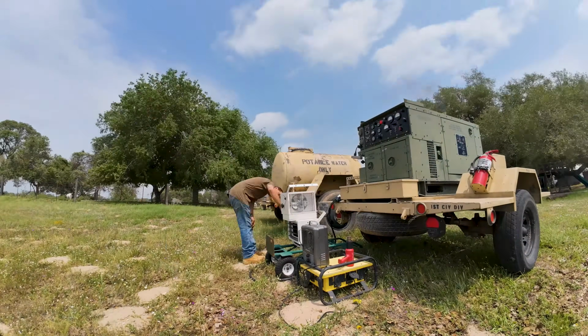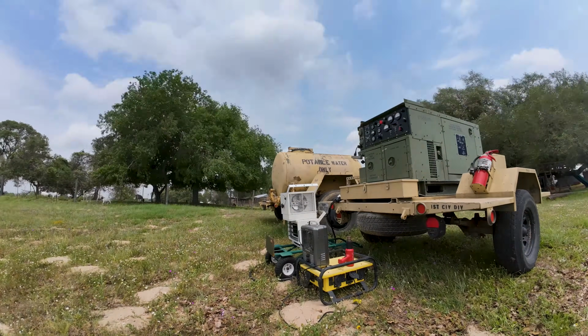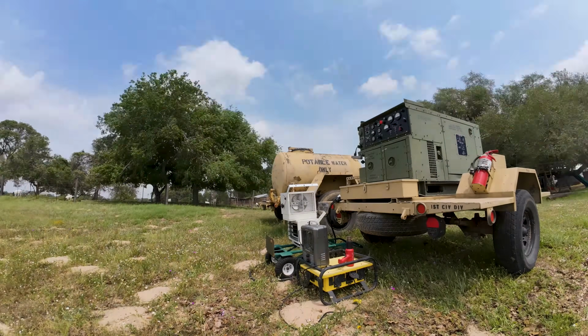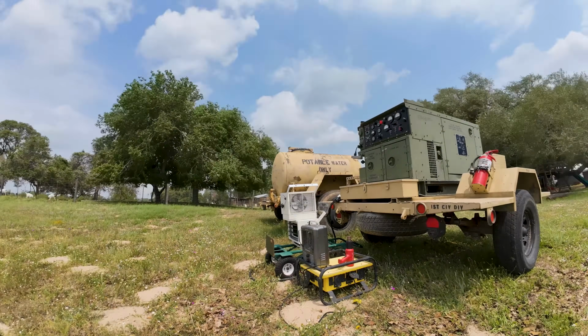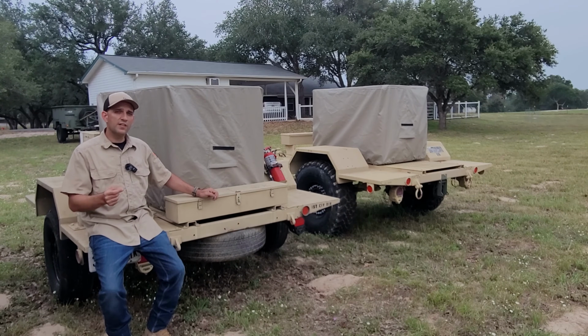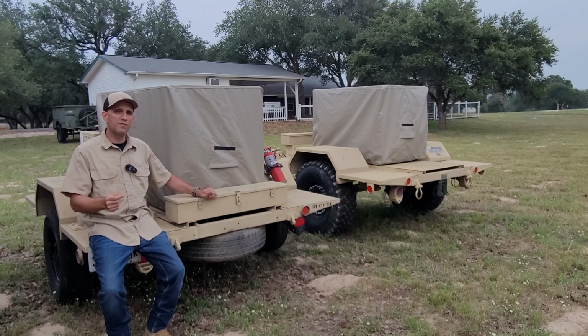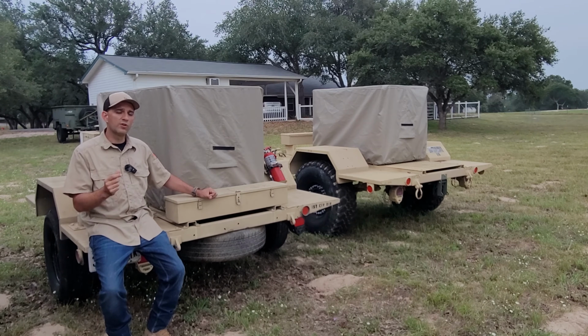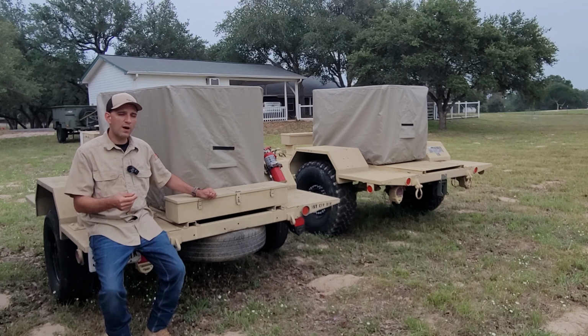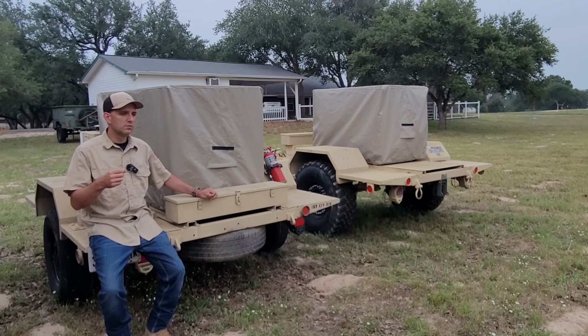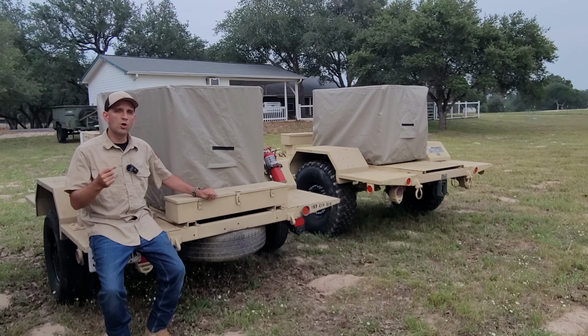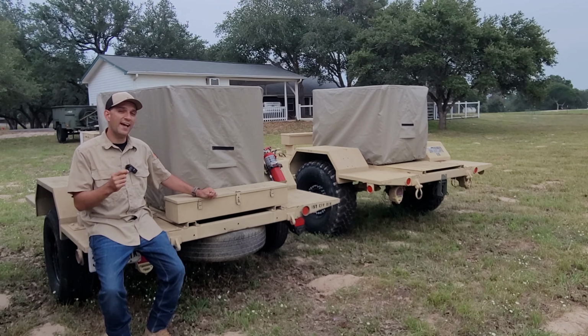Do the test for 6 hours, starting from when you hit 100% load or more, if you decide to do more. And if it fails during that time, you fix the problem that caused the failure and you start over again. So if you made it 2 hours and it failed, you don't fix the problem and then go 4 more hours. You start over again at that 6 hours.